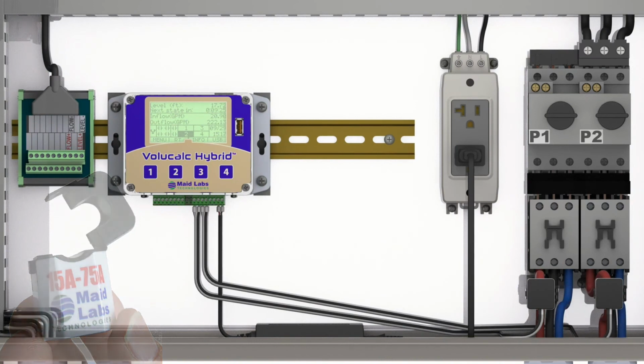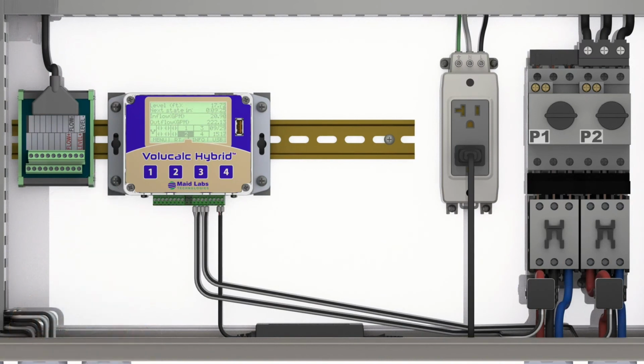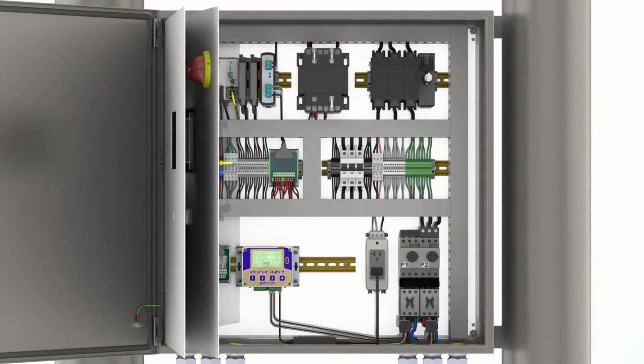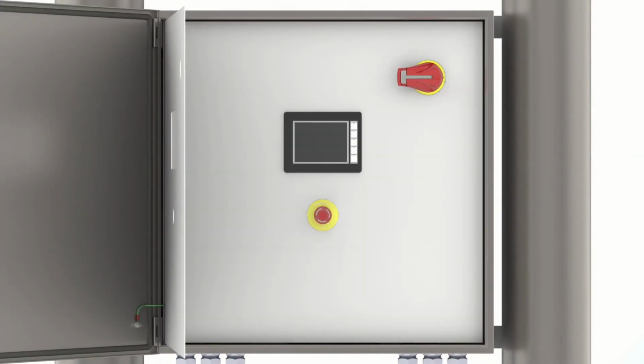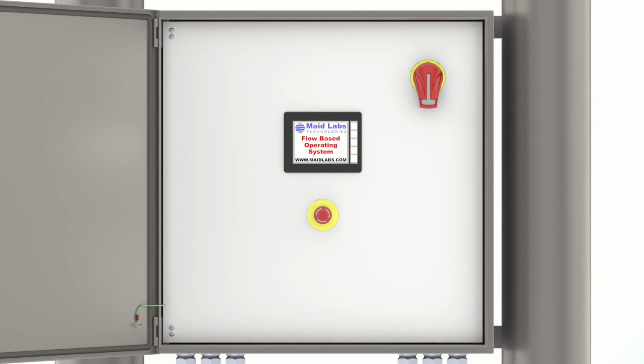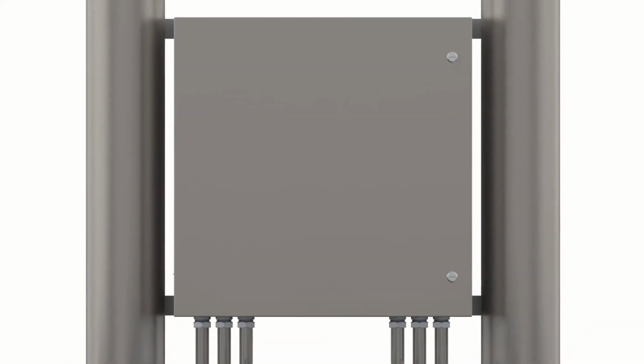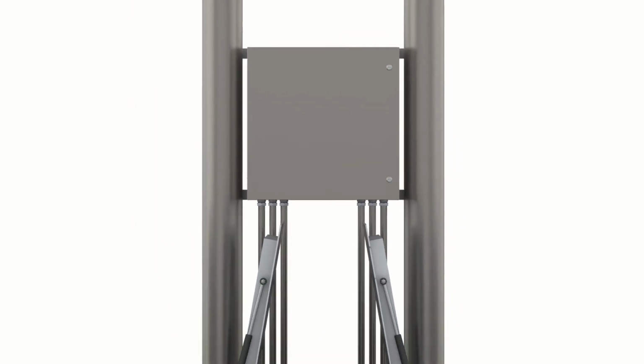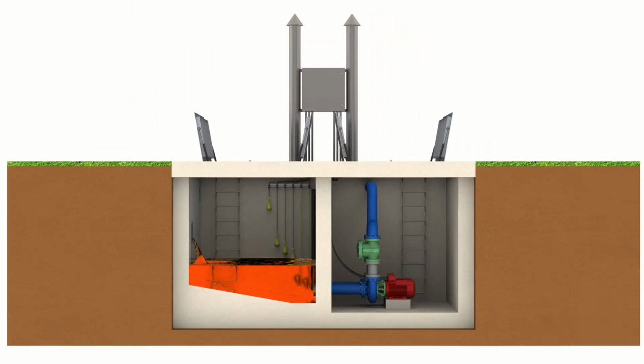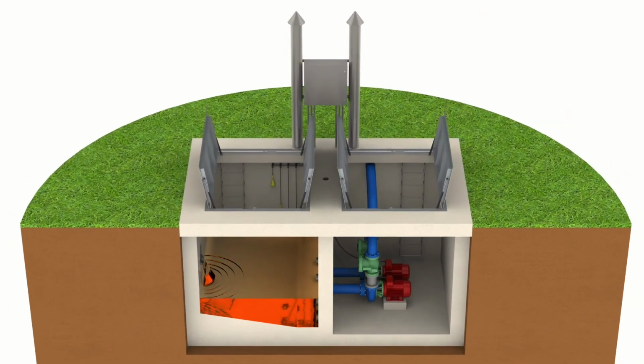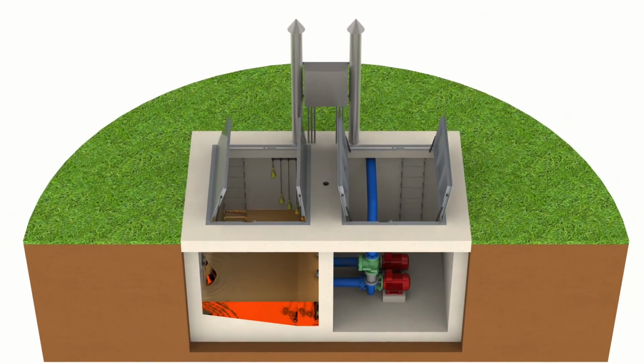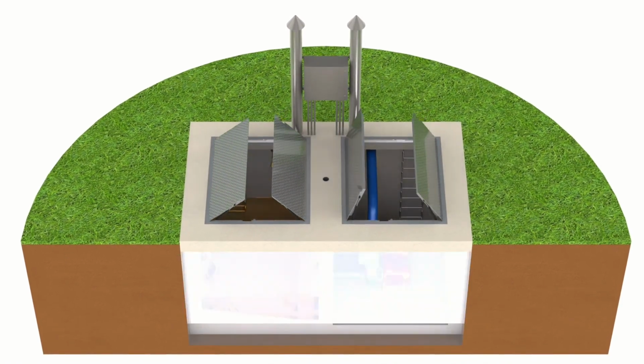After that, you need to set it up. If you have a level sensor, we suggest using a current isolator, so you piggyback on that level sensor, and you'll have quite a lot of information out of this. As you might have noticed, there are different ways of installing this instrument inside a control panel. When you have a lot of lift stations and you don't have a lot of budget, I strongly suggest that you keep it in your toolbox and move it around.